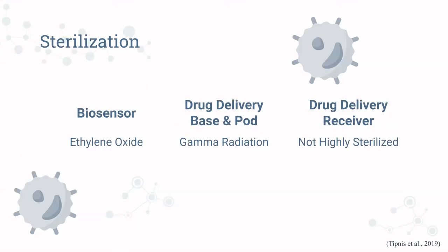Device components will be sterilized differently dependent on their material and risk of contamination. The biosensor will be sterilized by ethylene oxide using values found in the study sterilizing a similar coated biosensor for reading glucose. The drug delivery base and pod will be sterilized using gamma radiation at dosages safe for HDPE and COC respectively. Lastly, the receiver component of the drug delivery system will not need individualized sterilization apart from normal safety procedures, as this component is purely electronic and does not come into contact with the patient physically.